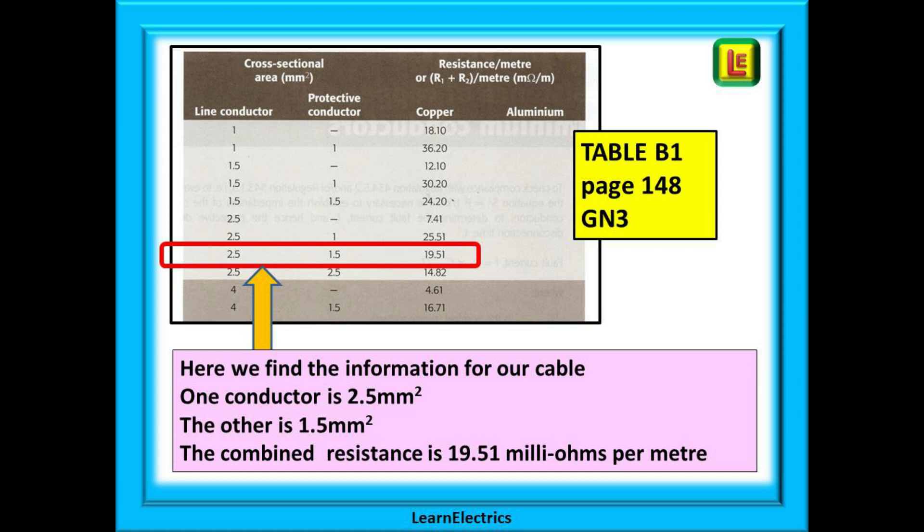Follow the first column down until you find the 2.5 mm section the CSA of our brown conductor. Now look in the second column and find 1.5 mm the CSA of the earth conductor. The third column will tell us the combined resistance for these two conductors as shown in the red box. It is given here as 19.51 milli ohms per meter.